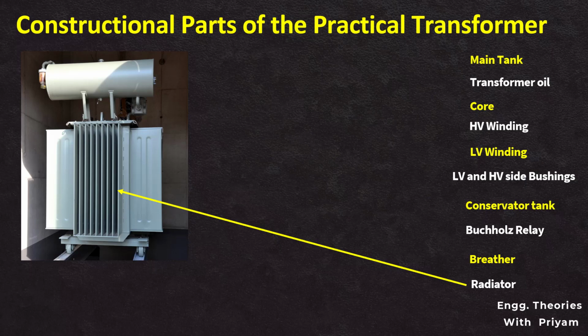As the air cools the oil, it becomes denser and falls, creating a natural convection current that drives the circulation of oil through the radiator. Transformers with high ratings often require a forced air cooling system to supplement the natural cooling process, ensuring efficient heat dissipation even under demanding conditions.